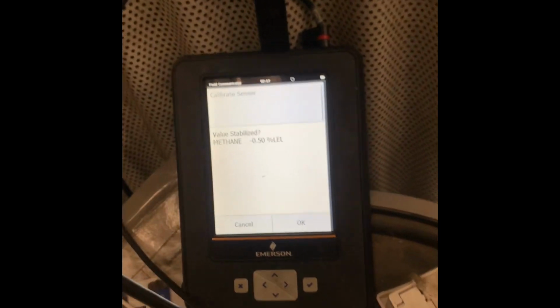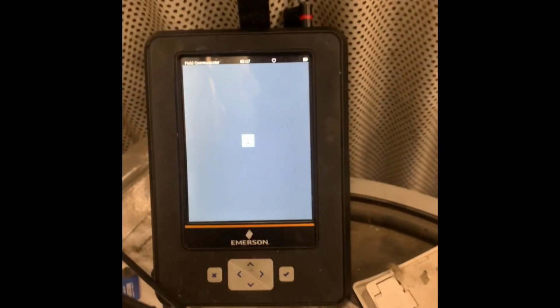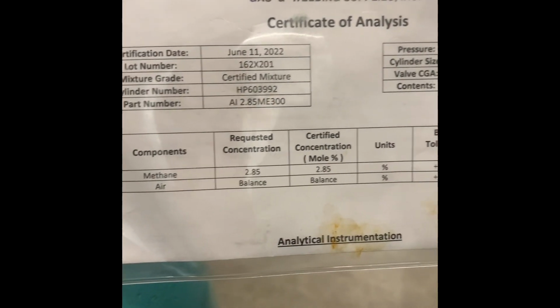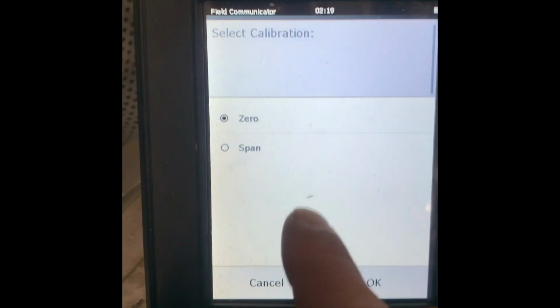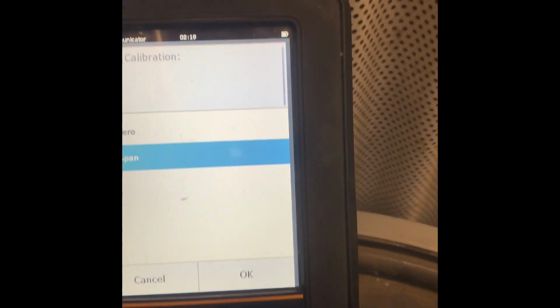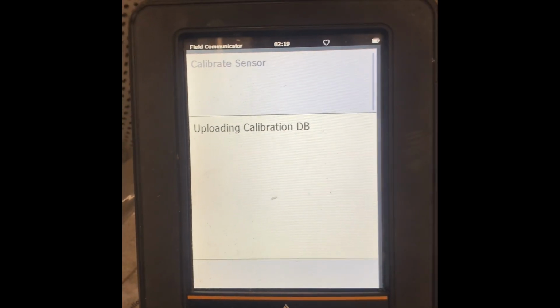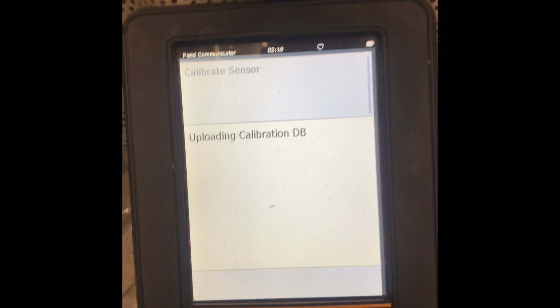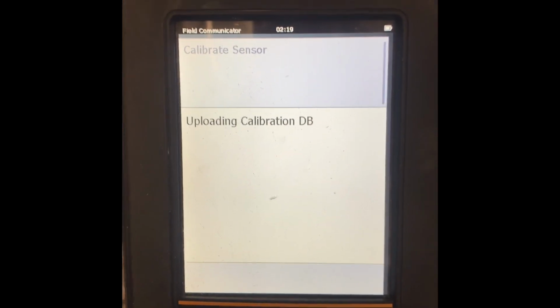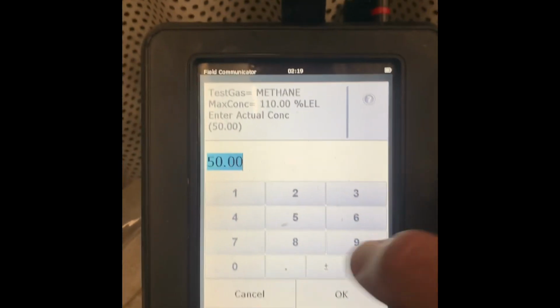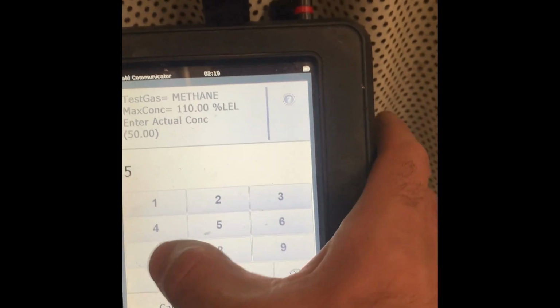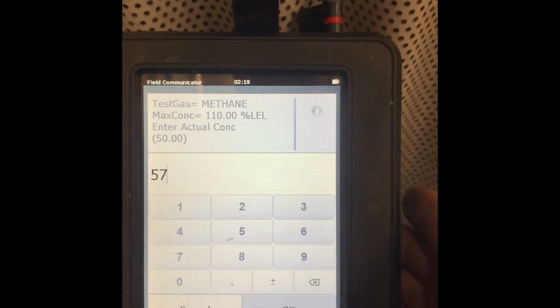Putting nitrogen through still. Alright, now when I do the span, I want to look at my bottle and see that 2.85, times that by 20, and you'll get 57, and that's what you want to put on your span. So when you go into your span mode here, I did cal it at 50, but this time it's going to be 57, just a different bottle.